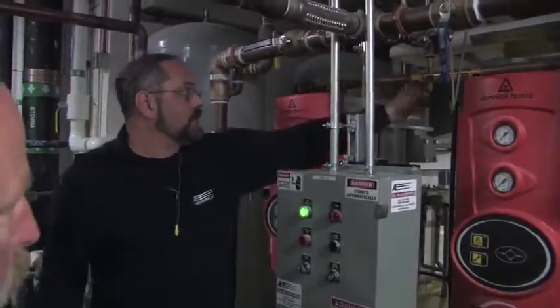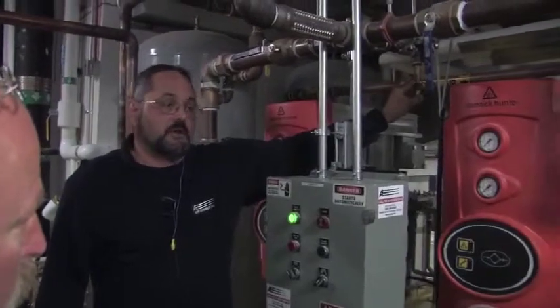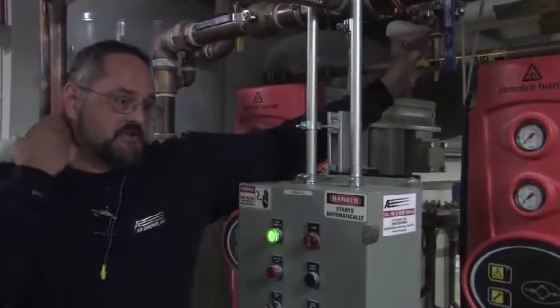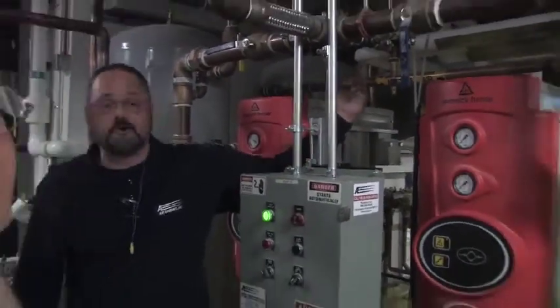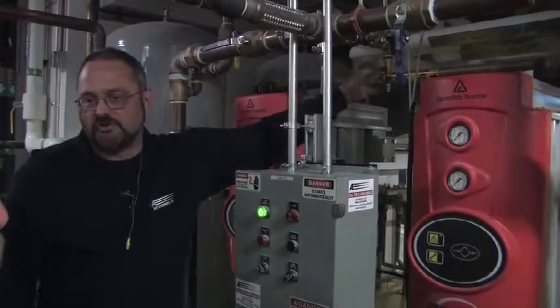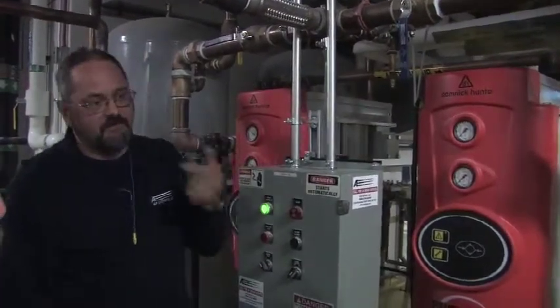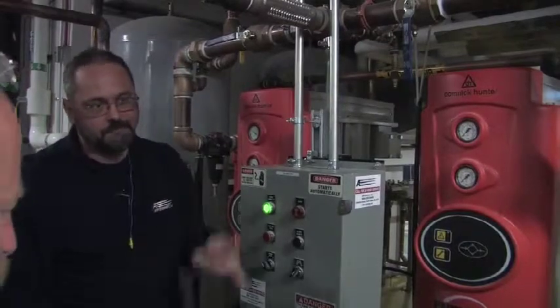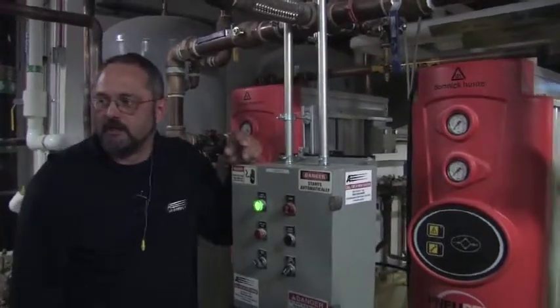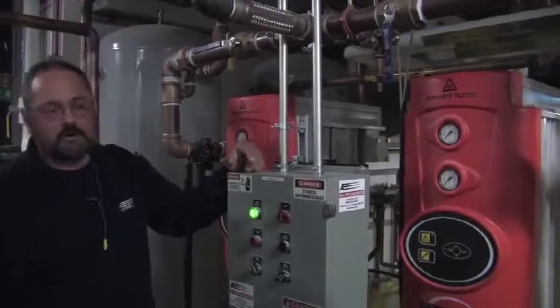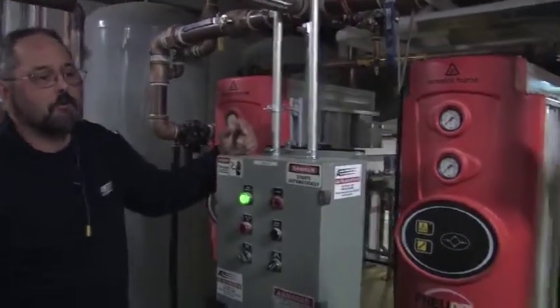But the other, there's a check valve in here, so that if you turn it off for some reason, the ambient air can't go back through and saturate the probe. That's usually the issue with these, is people turn them off, and even if you got a little pigtail on them, eventually some water molecules will get up there and saturate them. So put a simple low pressure check valve there.